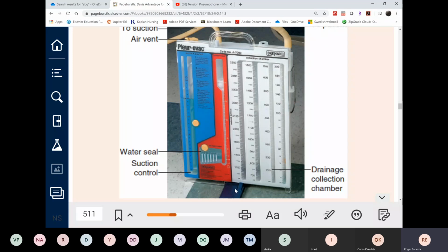Okay, and then this thing has a kickstand. When this is inside the sterile wrapper, of course, you can turn this 90 degrees. So this is parallel here in the package, and then when you take it out of the package, you simply turn it 90 degrees, and there's a lock here. So this is now your stand. Okay, so it's a kickstand. If let's say somebody messes with the kickstand, this thing can topple over. No problem, because let's say your fluid is all over the place. You simply tip this over to the right, and it will return all the fluid back to the original columns. There's really no problem.